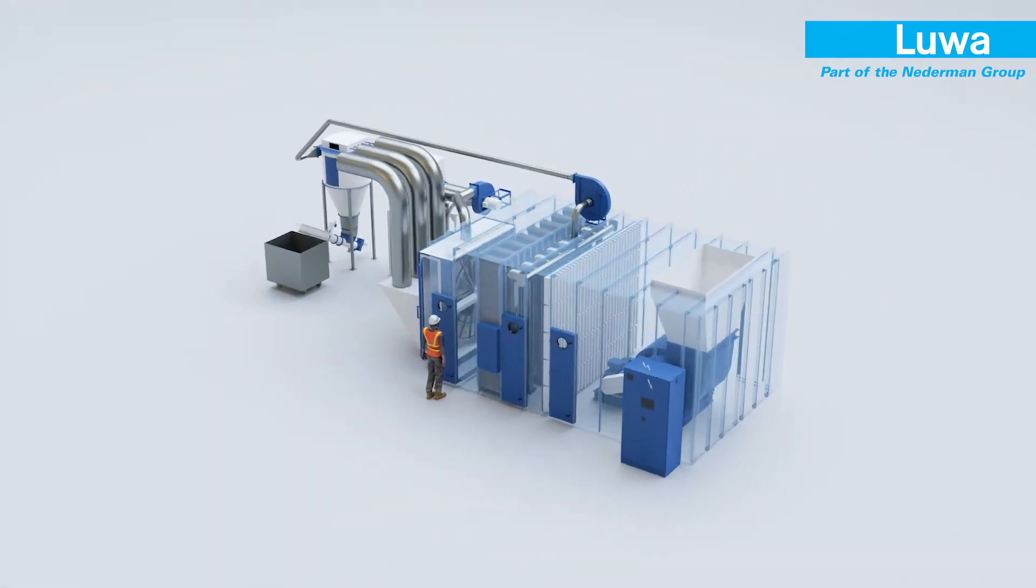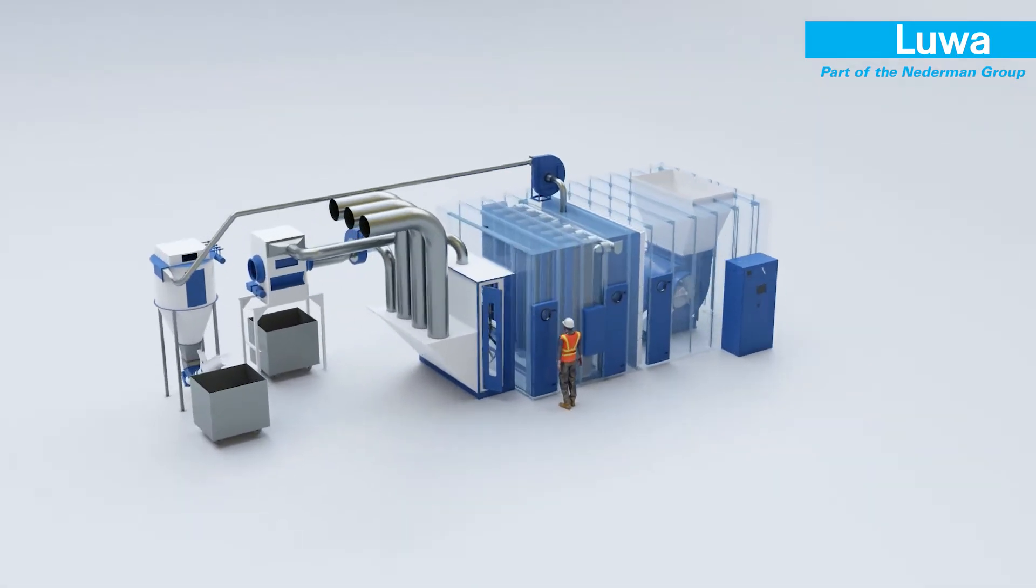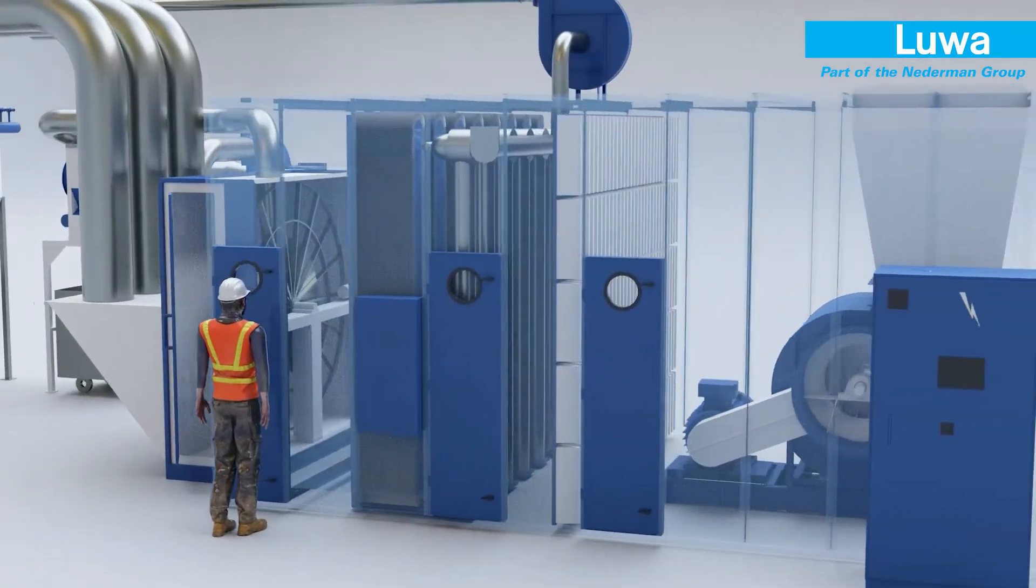Dusty air is captured on the rotary pre-filter screen from the vertical inlet. To minimize energy use, the screen disc only rotates when the pressure drop rises to a predefined set point.